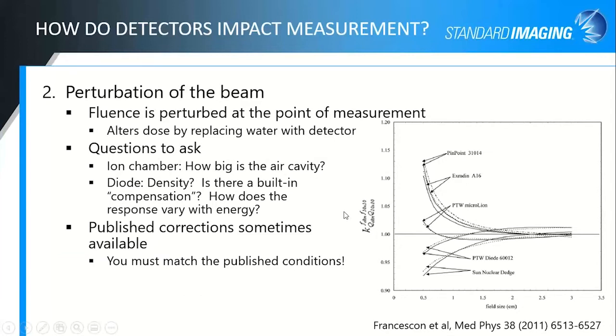Another way that detectors impact the measurement is by perturbing the beam. You're actually changing the way that the irradiation interacts right there at the point of measurement. You're altering the dose by replacing water with whatever detector you have, whether that's an ion chamber or a diode or something more like a scintillator or a diamond detector. So the things to ask when you're looking at these detectors, for something like an ion chamber, how big is the air cavity? How is that going to affect the size limitations where you can measure?